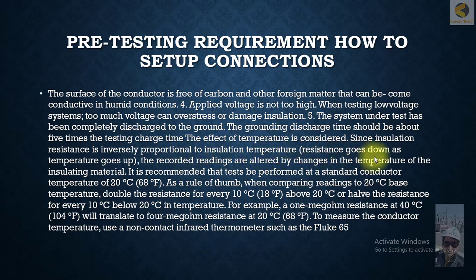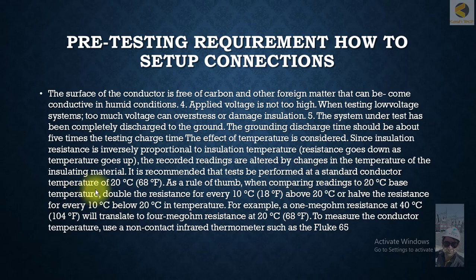The effect of temperature must be considered, since insulation resistance is inversely proportional to insulation temperature — resistance goes down as temperature goes up. The recorded readings are altered by changes in the temperature of the insulating material. It is recommended that tests be performed at a standard conductor temperature of 20 degrees Centigrade.